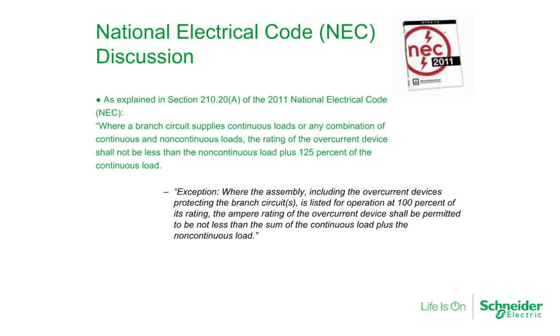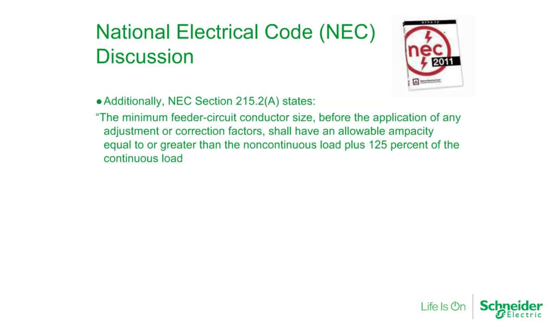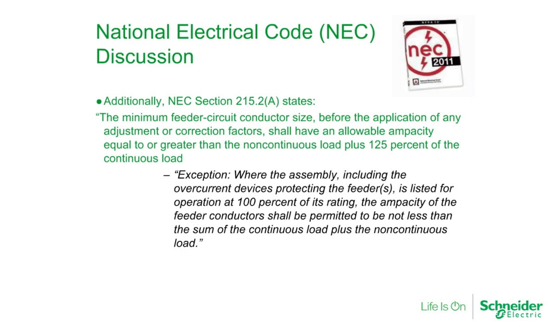UL specifies tests that must be conducted to obtain listings for continuous operation at 100% of the rated current. Additionally, another section from the National Electrical Code discusses the minimum feeder circuit conductor size. A standard 80% rated breaker and the equipment it is installed in and the connection wires have to be rated at the non-continuous load plus 125% of the continuous load. In contrast, a 100% tested and rated circuit breaker and equipment can carry 100% of the sum of the continuous and non-continuous loads.